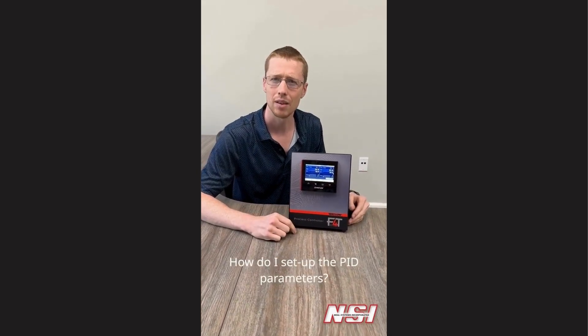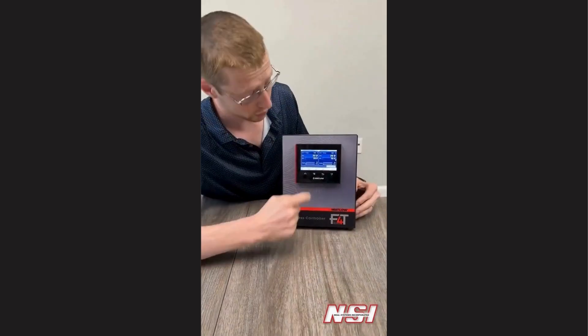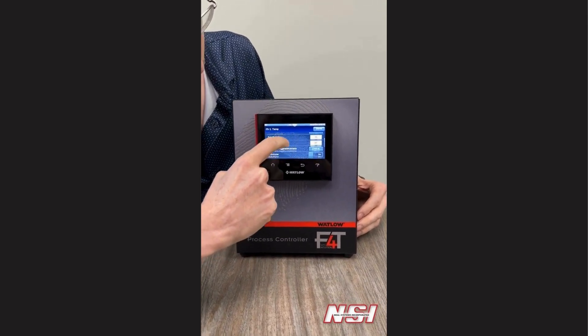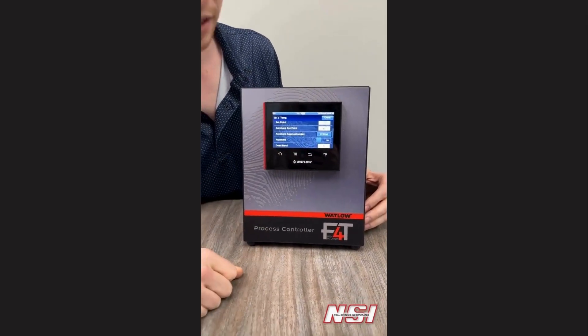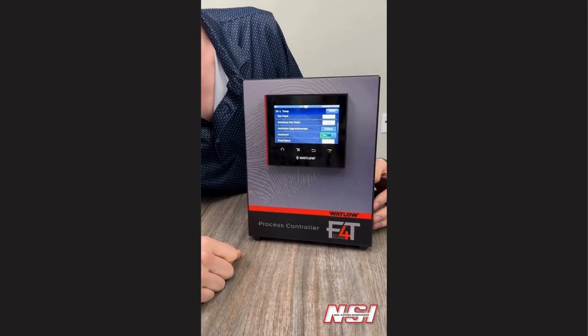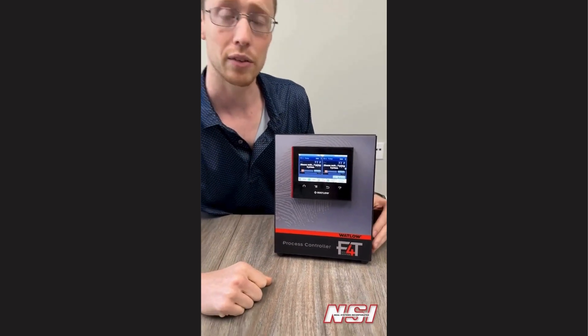How do I set up the PID parameters? Thankfully, we have something called Auto-Tune. You'll click on the initial temperature that you're trying to measure, and you'll scroll down to the Auto-Tune button. Once you're ready to hit the Auto-Tune button, you'll press this here. It'll tell you Auto-Tune Yes, you'll hit Done, and you'll notice the system is processing. During this time, the system will perform an Auto-Tune to the set point that you desire.